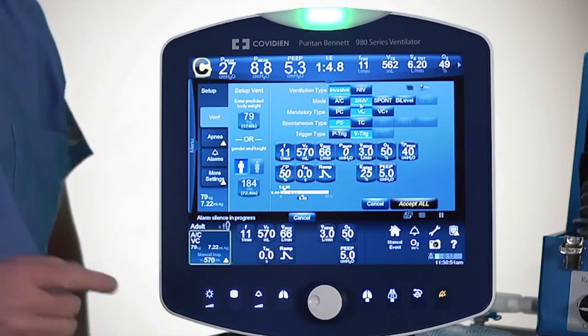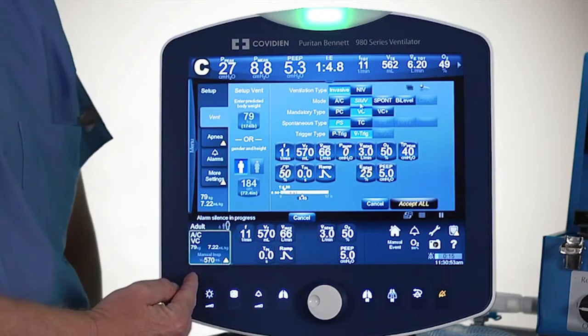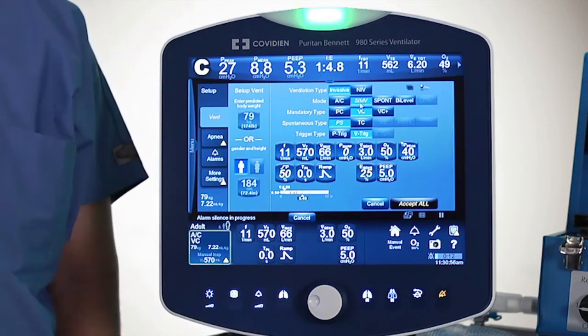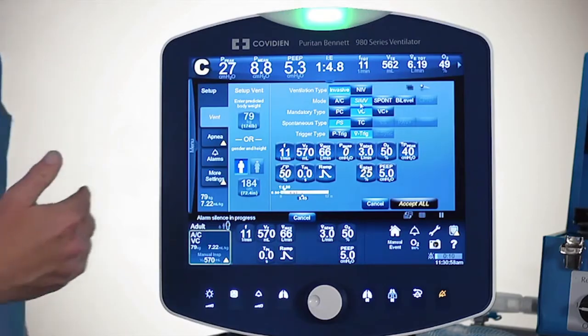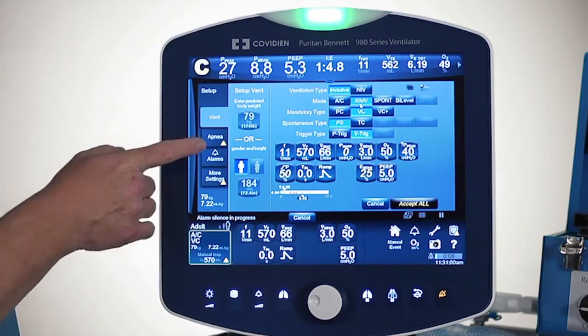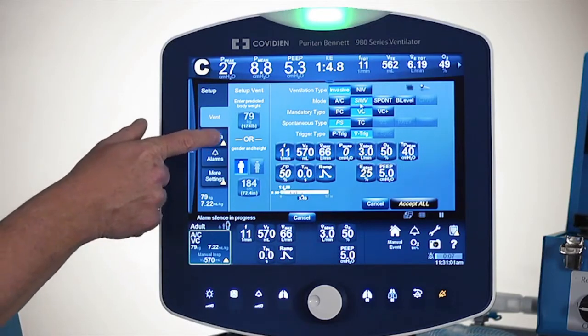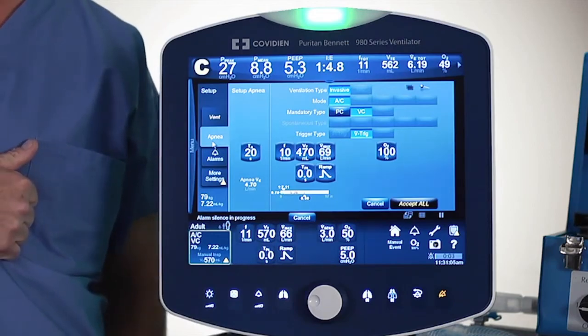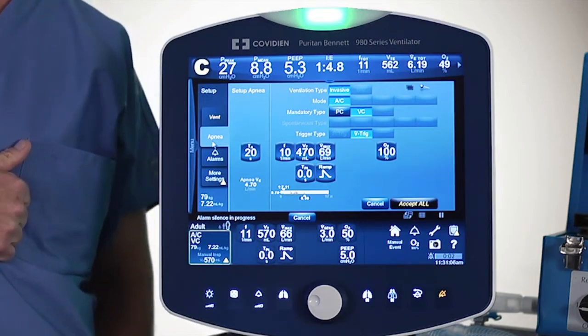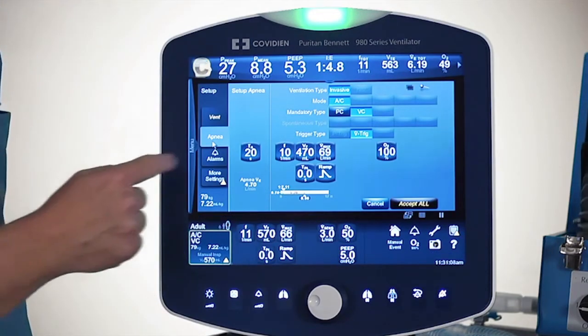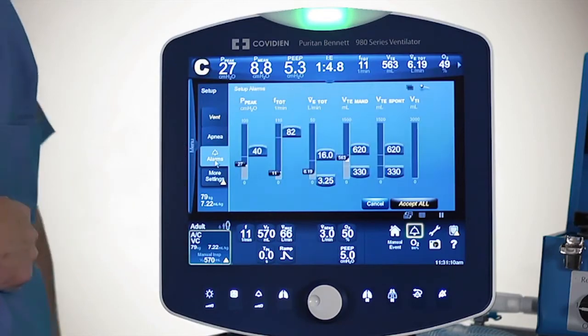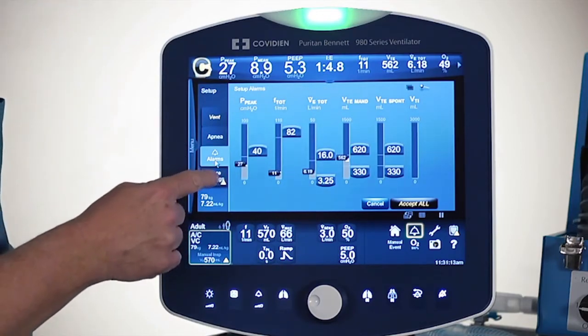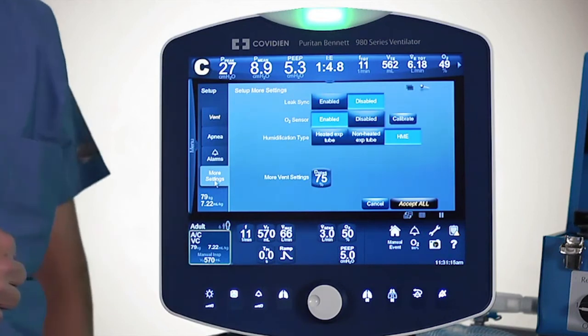In addition, when you touch this vent setup button on the lower left hand side, it also brings up a number of tabs on the left side of the screen. On the left side of the screen, there is also the ability to go in under the apnea information where I can set my apnea settings, and I'll talk more about that in a minute. I can go into alarms as well on this area, and there's also a more settings area.